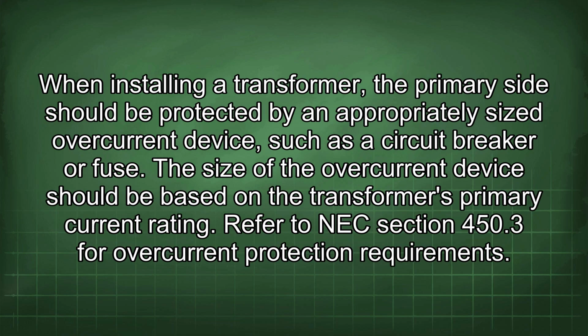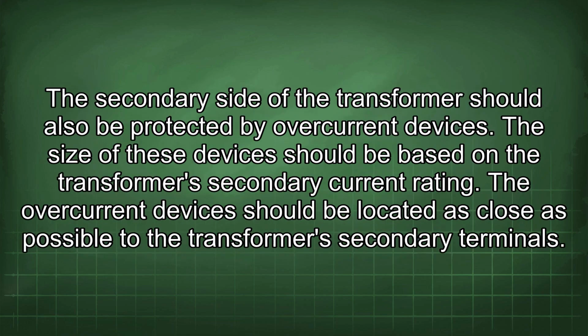When installing a transformer, the primary side should be protected by an appropriately sized overcurrent device, such as a circuit breaker or fuse. The size of the overcurrent device should be based on the transformer's primary current rating. Refer to NEC section 450.3 for overcurrent protection requirements. The secondary side of the transformer should also be protected by overcurrent devices. The size of these devices should be based on the transformer's secondary current rating.